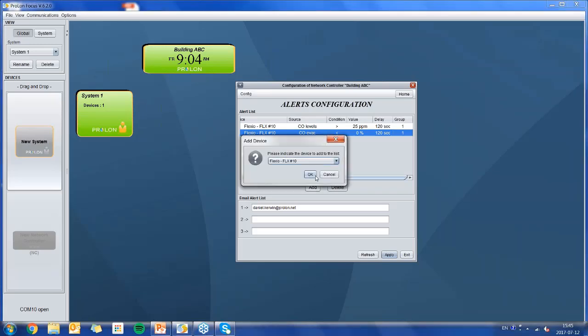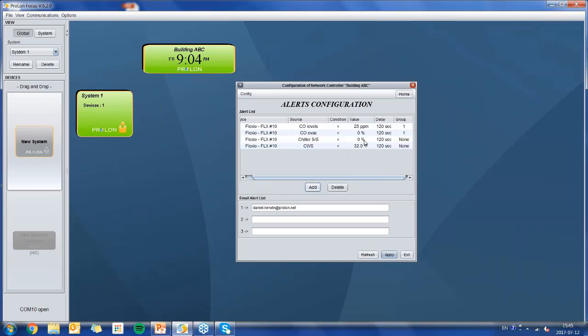Let's say I look at another one: my chiller with the cold water supply. If my chiller is on, and my cold water supply continues to be above 50 degrees, which is not what I want because my set point is 40, and maybe this has been true for a bit more time here. So in this instance, if my chiller's been on for 6 minutes and my cold water supply is still above 50 degrees, now I want an email, and we can send it to up to 3 different email addresses as well. So once again, you choose.